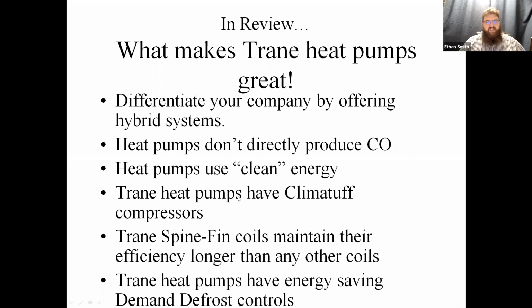When we're talking about these hybrid systems, guys, this is what is also referred to in the industry as dual fuel. A lot of times, it means that you're using either propane or natural gas along with the heat pump. Be aware of that. If you're using a furnace as your supplemental heat, you can't run the heat pump and the supplemental heat at the same time, because your indoor coil is downstream of the heat exchanger in those installations. So be aware of that, guys. So make sure you're not putting a 6-ton or a 5-ton heat pump and expecting to be able to replace all of its heat with a 40,000 BTU furnace. It's just not going to happen. In addition to the fact that you wouldn't be able to make airflow. So be aware of that, guys.